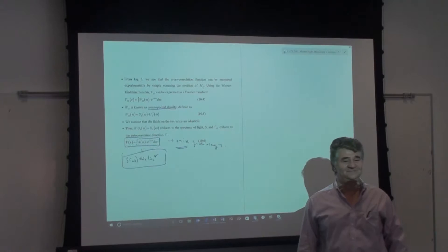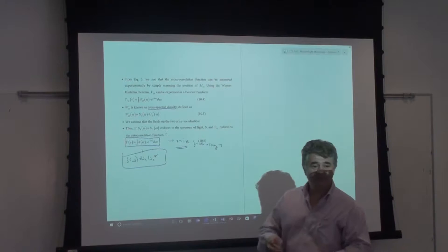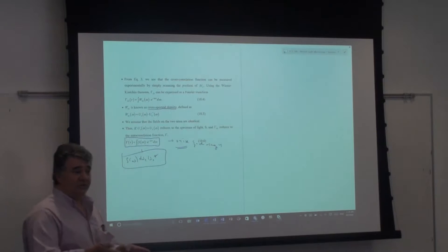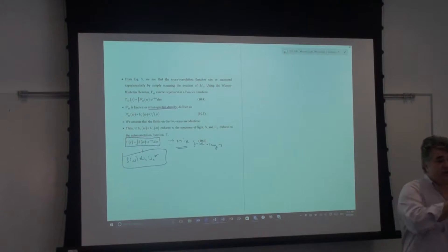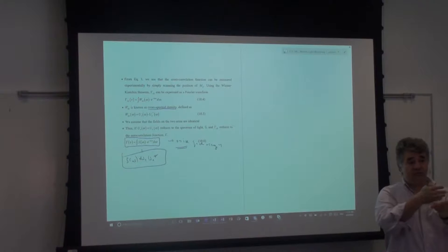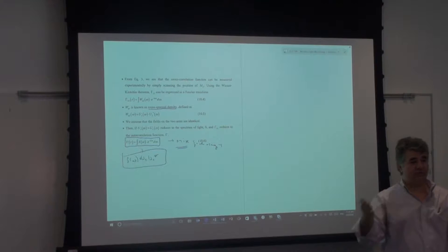There are applications where measuring in the time domain is advantageous. For a dispersive spectrometer, spectral resolution depends on how fine the grating is. For this interferometric measurement, spectral resolution is determined by how far you scan the mirror in τ. By the Fourier uncertainty principle, to get fine sampling in ω you need a large τ range. The resolution scales as Δλ/λ ~ λ/Δz — so scanning over a millimeter at 1 μm wavelength gives 10⁻³, i.e., ~1 nm resolution, and over a meter that improves by another factor of 1000.